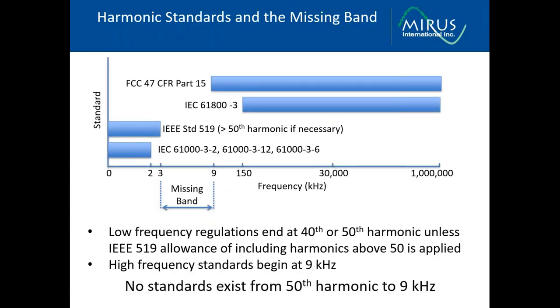Next, let's have a look at the standards that have been adopted for limiting harmonics. At the low end, up to, say, the 40th or 50th harmonic, we have IEEE standard 519. IEEE standard 519 defines the harmonic limits up to the 50th harmonic, but also states that higher frequencies can be used if necessary. But most people apply IEEE 519 at the 50th harmonic or below. So at 60 hertz in power systems, 50 times 60 gives you 3 kilohertz. So that applies to harmonics up to 3 kilohertz.